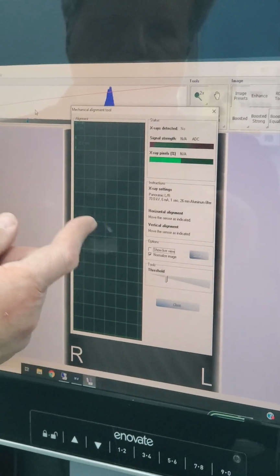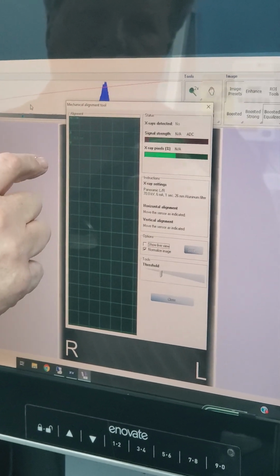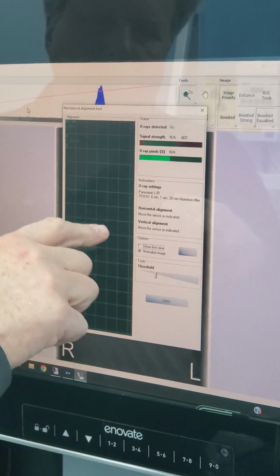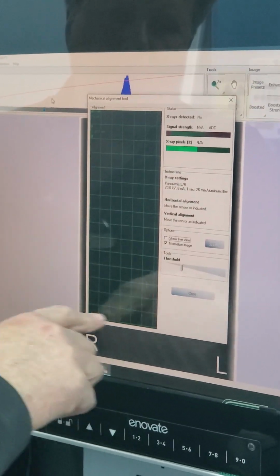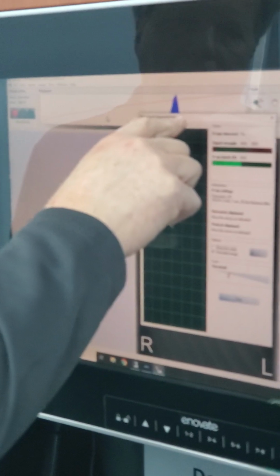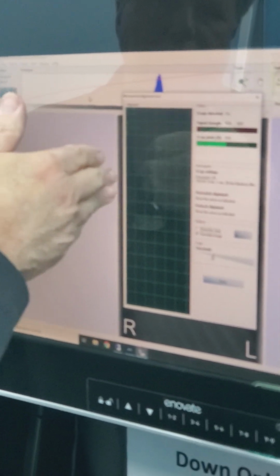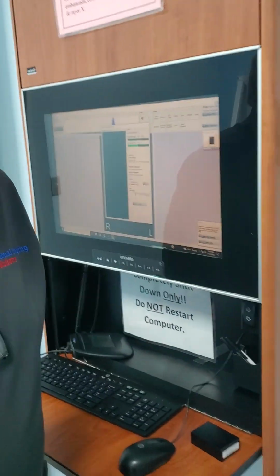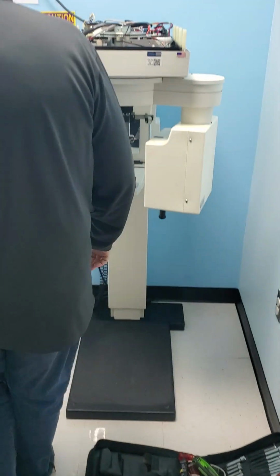And what we're looking for is ideally 3 green numbers, which is the alignment left and right here, the alignment left and right at the top, and the alignment up and down. But practically, we want to see space on this side of where the beam hits and space on this side as well. So we want the beam to be somewhere between the 2 margins of the sensor. That slot, right? Yeah. This represents the slot, the sensor space. And when we shoot, it's going to show us where the beam is hitting.